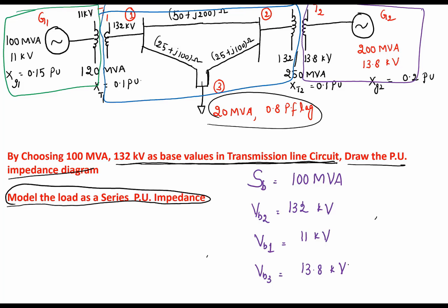Understand? So now we know our base MVA and all three base voltages. So on these new base values, we have to compute the per unit impedance of each and every element. Now first, what is the first element? In the first section, the element is generator G1. So what is the per unit impedance of that one on these new base values? Already on the machine ratings of 100 MVA and 11 kV, they have calculated the per unit impedance, whose value is 0.15 per unit. Fortunately, our base MVA rating and our base voltage are exactly matching with the machine MVA rating and machine voltage rating. So here the new base values and old base values are exactly the same. So the new per unit value will be the same as the old per unit value. So we need not calculate.